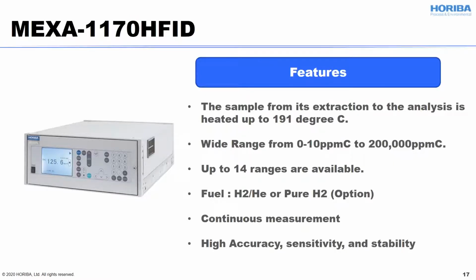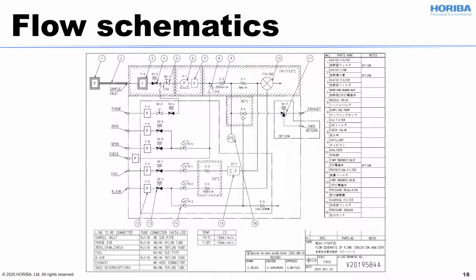You can select the fuel from a hydrogen 40% helium 60% base mix or pure hydrogen. It is designed for continuous measurement with high accuracy, sensitivity, and high stability. Here is the flow schematics. From the probe, the sample gas temperature is kept at 191 degrees C or above. Then it comes into the analyzer box, which is also heated.